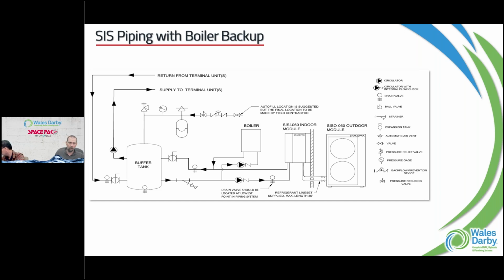We can work with the boiler a couple different ways. Maybe the buffer tank's just not keeping up, so we have a differential set point - if it gets to that lower range, it'll kick the boiler in and ask for help. We also have the ability, based on outdoor temperature, to hand it off to the boiler, and now the boiler is the one that maintains the temperature of the buffer tank.